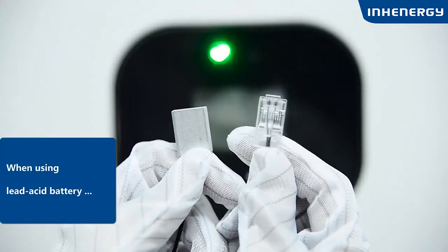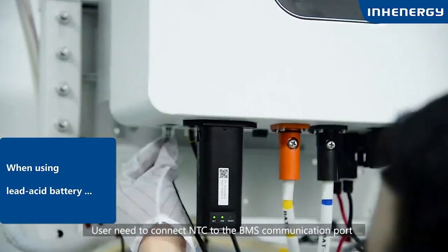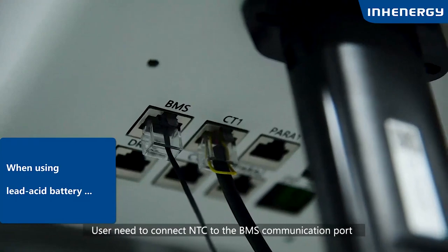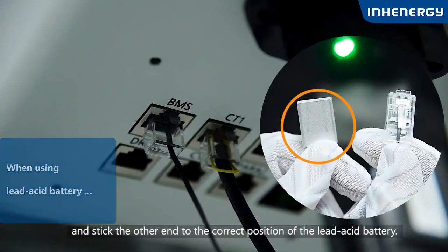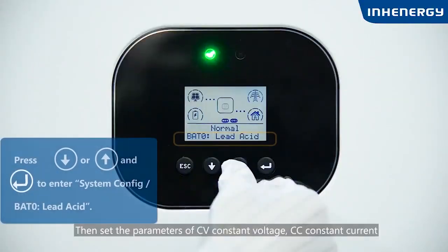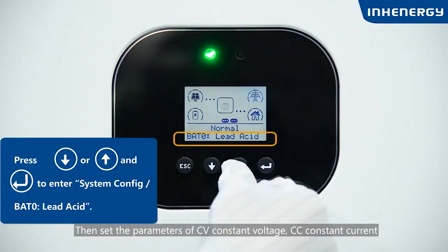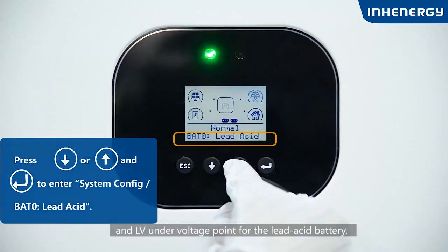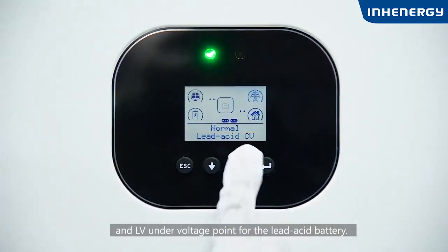When using a lead-acid battery, user needs to connect the NTC to the BMS communication port and stick the other end to the correct position of the lead-acid battery. Then set the parameters of CV constant voltage, CC constant current, and the LV under voltage point for the lead-acid battery.